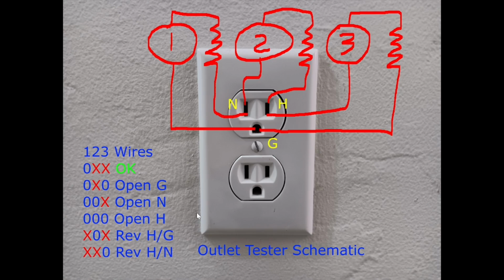And one thing to keep in mind about these simple outlet testers is they can't test for every possible condition that could be wrong with an outlet. So even if an outlet tester says that the wiring is okay, it's only testing these wiring conditions. An example of some conditions that a simple outlet tester can't test for is a reverse neutral ground. It also can't test for a bootleg ground. That's when there is no ground, but somebody inside the outlet connected the neutral to the ground, so it looks like there's a ground when there's not. And there's also other conditions that a simple outlet tester can't test for. So I just wanted you to be aware of that.